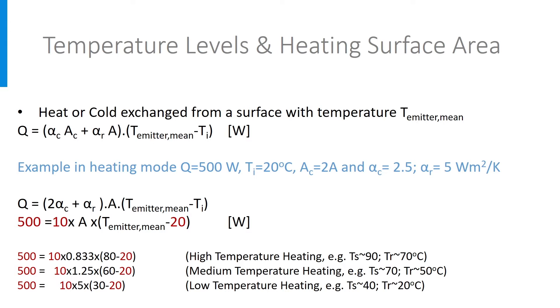So, the lower the temperature of the radiator, the higher the needed surface area. The temperature levels given here correspond to what we call high temperature heating, medium temperature heating, and low temperature heating. In low temperature systems, in general, floor heating is applied in order to have enough heat exchange surface area.